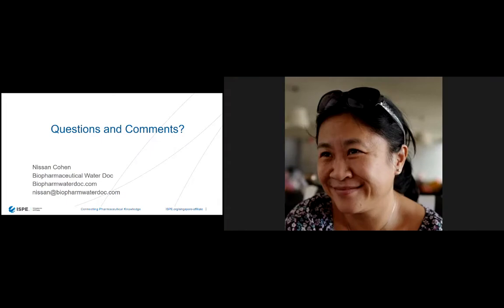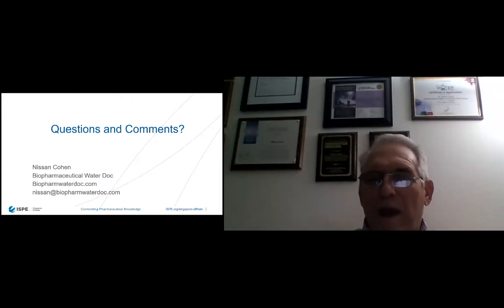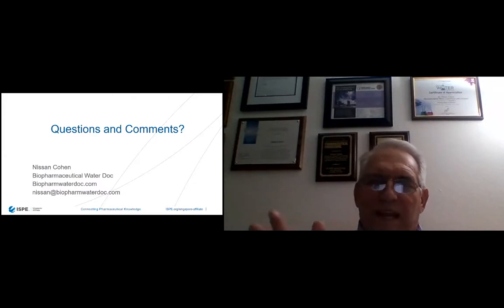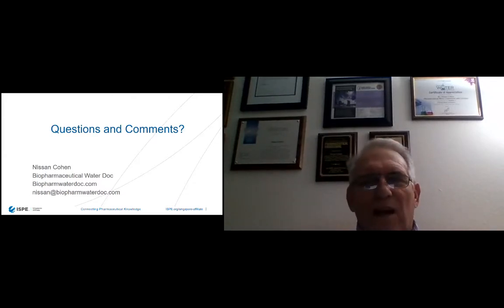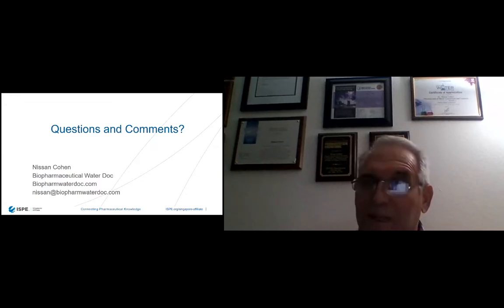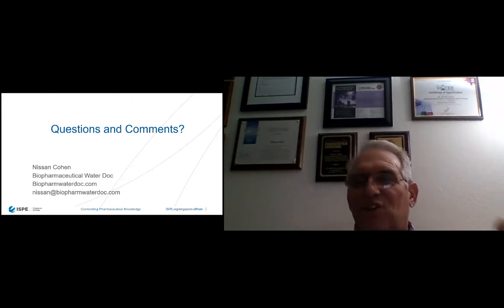We have a lot of questions. Fu is asking, based on the Rouge monitoring data, what is the limit in nanometers that should trigger the derouging process? Depends on your system and how great your Rouge is developed in your system. What you need to do is make a limit that makes sense. You know, is 1 micron a level that you want to do derouging passivation? Maybe. Is 0.5 micron even better? Maybe. Will you still get Rouge or get unsightly Rouge inside the system? The answer is probably. How does that look in the system? It may be a discoloration, but the point is as the Rouge develops, you have a way to monitor it, in order to make a determination.